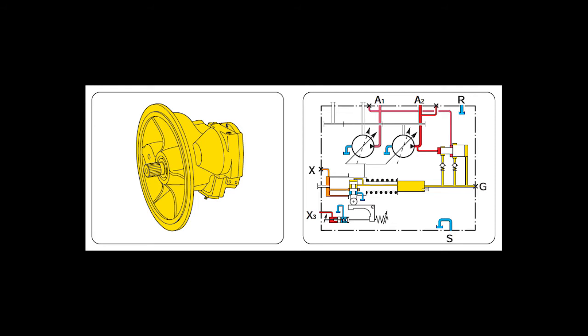SR Summation Power Control Hyperbolic Regulator. The Summation Power Control SR is a pressure-dependent pilot-operated control which steplessly adjusts the coupled rotary groups, thus varying the displacement. The swivel range is from VG max to VG min.